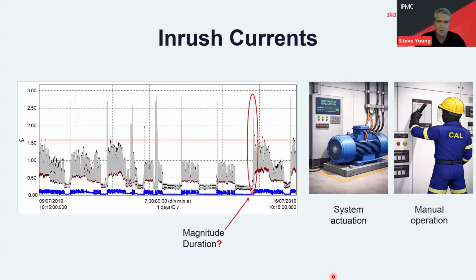Yeah, thank you, Dan. It's a good point. So if we've got a voltage dip, we need to try and understand a bit more about where it comes from. Through applying good measurement and analytics of that data, we can analyze inrush currents, short duration currents, and potentially tie them back in through data analysis to the voltage dip event. So for instance, if we have an automatic operation of a large induction motor, that can create an inrush current, and of course, in an Ohm's law relationship, it will go across the transformer and create a voltage dip at the same time. So that's an automatic system actuation, if you like. But similarly, it could be a manual operation, a manual switching that creates that inrush current event on the network.